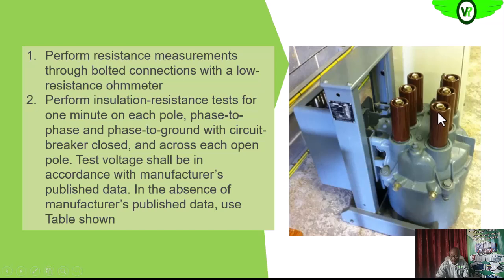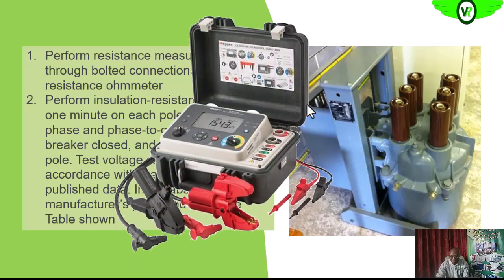So that will give us the effective insulation resistance of the insulating material, which is the oil in this case now, in the circuit breaker. So we'll test for the first contact for line 1, test for the second contact, and then the third contact. So we want to be sure that all of them meets what is specified by either the manufacturer or one that is specified in our facility. So in case that we do not have, we can use this table as shown.